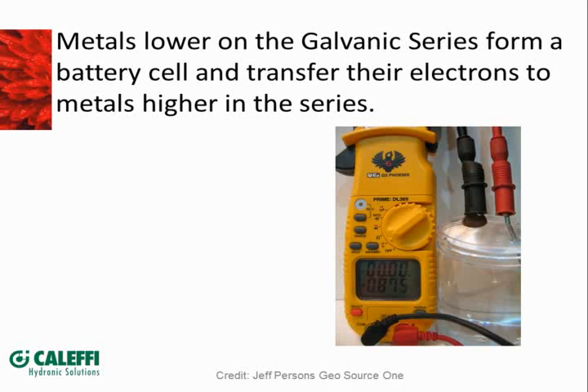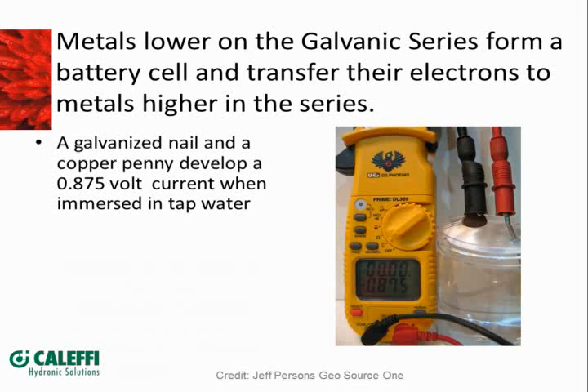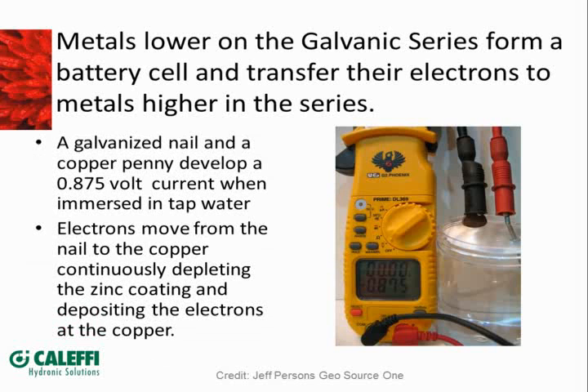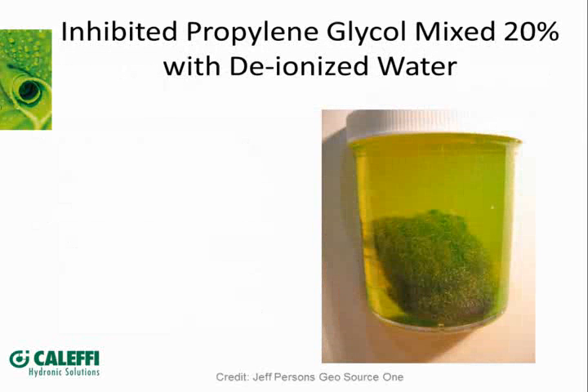When you have two dissimilar metals mixed in a solution, you can always set up a galvanic or battery cell. In this slide, we have a penny tied to a digital ohm meter or voltmeter and a galvanized nail, both sitting in city water. There's a voltage reading of 0.875 volts, wherein electrons transfer from the zinc coating on the nail over to the copper penny. We see the same type of battery cell exists inside our hydronics.